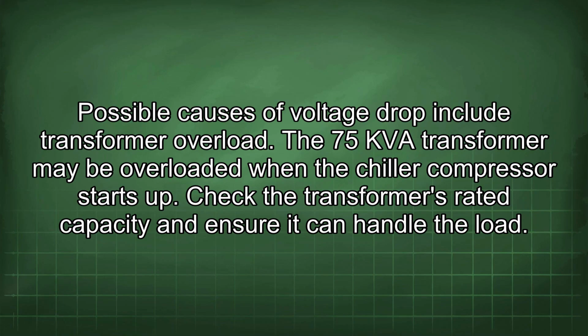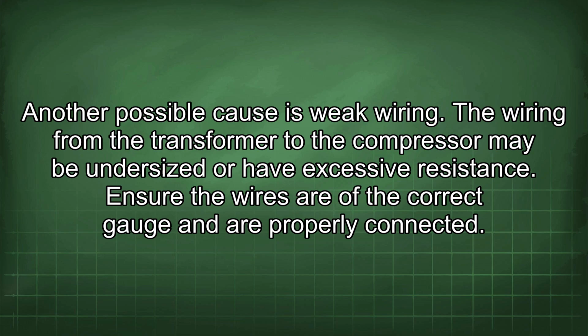Possible causes of voltage drop include transformer overload. The 75 kVA transformer may be overloaded when the chiller compressor starts up. Check the transformer's rated capacity and ensure it can handle the load. Another possible cause is weak wiring. The wiring from the transformer to the compressor may be undersized or have excessive resistance. Ensure the wires are of the correct gauge and are properly connected.